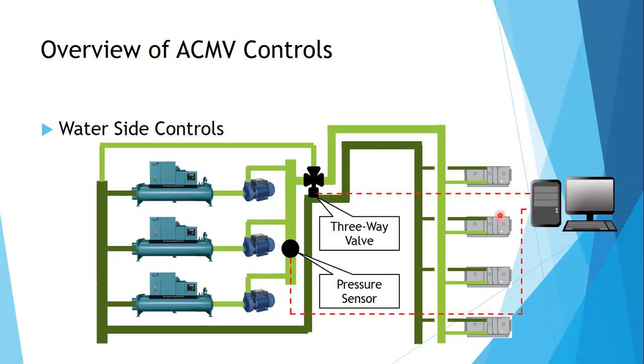But like our example before, this one air handling unit is in maintenance mode or turned off. What are we going to do? So if this is turned off, the pressure sensor will detect an increase in pressure, and this three-way valve will bypass or will release the extra pressure back to the chiller.